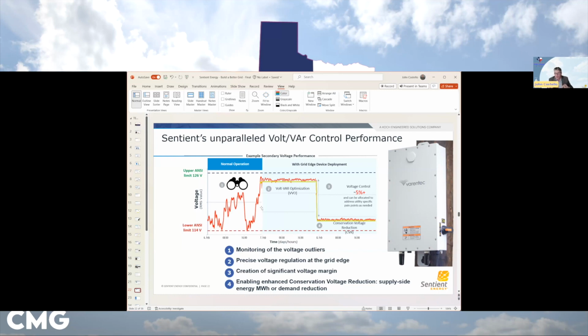This is a capacitor-based solution rather than an inverter-based solution - all we're doing is putting vars in. We're able to get that range really tight. That's what we call control on the optimization side, getting that bandwidth so there's not as much fluctuation.